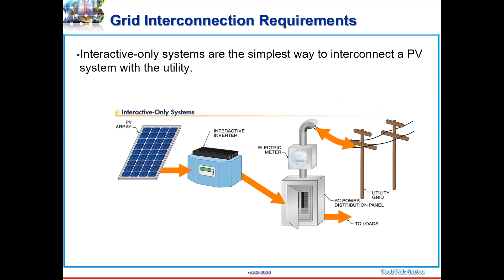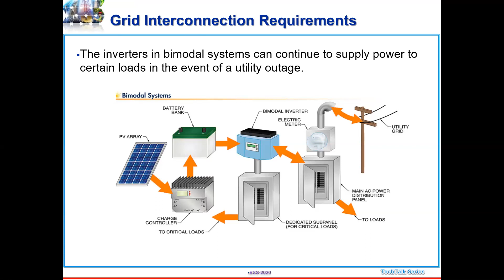Several difficulties will come into the picture when you have battery storage, because in the other case, once the grid is not there, the solar PV will be disconnected and go out of the system. But here, even though the utility is out, the PV system and the inverter will be maintained. They will maintain supply, so you have to bring higher protection systems into play. It will create some problems in the network.